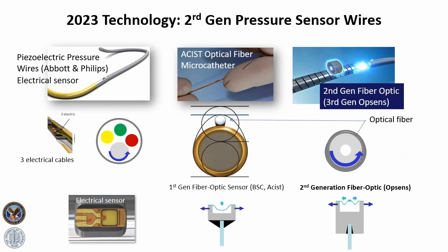I think Philippe told you the differences between these wires. Here are the three categories. The piezoelectric wires on the left have a sensor. They had some problems early on, but they're much better now. The middle panel was the ACIST fiber optic microcatheter, developed so you could use your own wire, which you liked a lot, and then have a pressure sensor delivered over it. You get your information at the cost of a slightly increased cross-sectional diameter. It's not a bad thing.